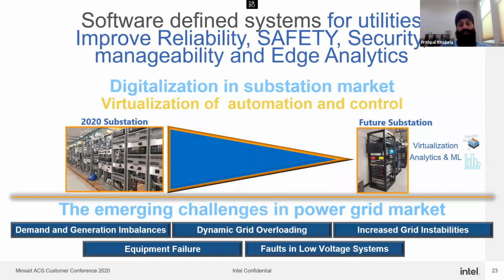Here is the idea of how to move forward: a software-defined system. We need to standardize the hardware for the substation market in order to optimize access to renewables. The best approach is to take away the fixed feature-function devices and replace them with a rack of rugged hardware, using IEC 61850-3 Class 2 or IEEE 1613 certified servers.